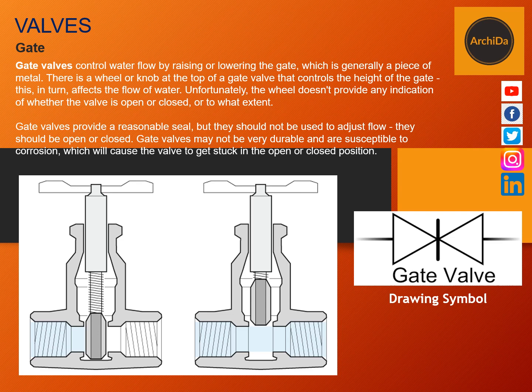Next, we have what is called a gate valve. This is usually located on the main, right before it branches off to several uses — in the kitchen or in the toilet, it branches off on the kitchen sink, the lavatory, the shower stall, and the water closet. Gate valves control water flow by raising or lowering the gate, which is generally a piece of metal. There is a wheel or knob at the top that controls the height of the gate and affects the flow of water. Unfortunately, the wheel doesn't provide any indication of whether the valve is open or closed or to what extent.